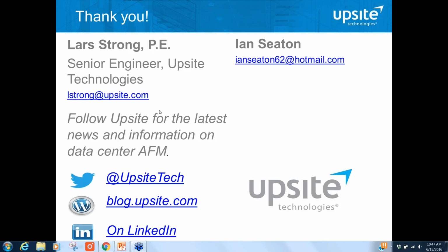No worries. There'd actually been some research done some number of years ago by Dell, and they had published a couple papers on this where they looked at the cumulative pressure drop effect of those articulating cable management arms and how they consolidated cable often in the path of the server fan exhaust and the effect on the operation of those servers. Our recommendation has always been to not use those.